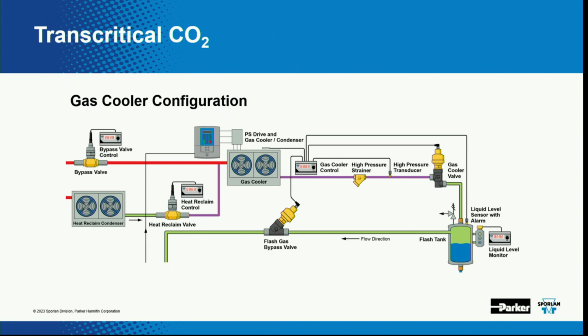If we want to get some heat reclaim, it goes through a heat reclaim loop, and that's being controlled by a modulating valve, or we can run it straight into the gas cooler, or a little bit of each. And that's our gas cooler. That's got our fans on it. It's blowing air. It's on the roof. And yeah, that's what's going on. It's not a condenser, because if it was a condenser, it would be condensing something inside of it. And it's not condensing anything inside of it. It's just cooling it down. So that's why we call it a cooler.